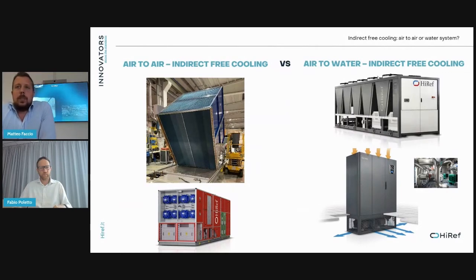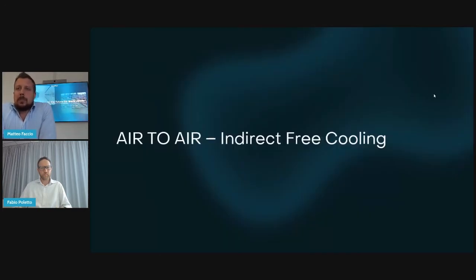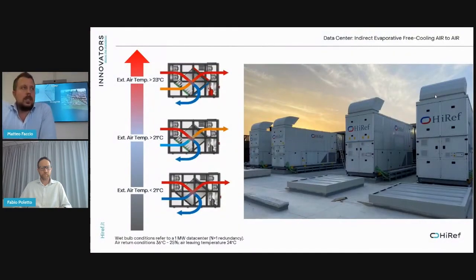In indirect free cooling, we have two main systems to use: the air-to-air indirect free cooling and the air-to-water indirect free cooling. Let's start by having a look at the air-to-air solution. I'd like to start by looking at this picture, which is a real installation we have done in Europe. The unit in the picture is a 3-in-1 system, which means this unit is able to work in 3 different working modes. The most used one is the dry free cooling, when the external temperature is lower than 21. This way, the big cross-flow heat exchanger inside the unit gives the opportunity to transfer the cooling capacity from the external air to the data center airflow volume.